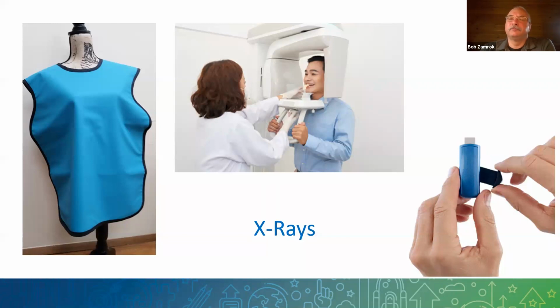disinfectants. Thank you, Bob. And we've seen it on Panorexes too a lot, on both 2D and 3D. We've replaced panels and covers on a lot of machines, and most of it comes back to disinfectant use that just corrodes the plastic and makes it brittle. Disinfectant use outside of the recommendation by the manufacturer. That's really what you're saying, right? Correct. Yes.